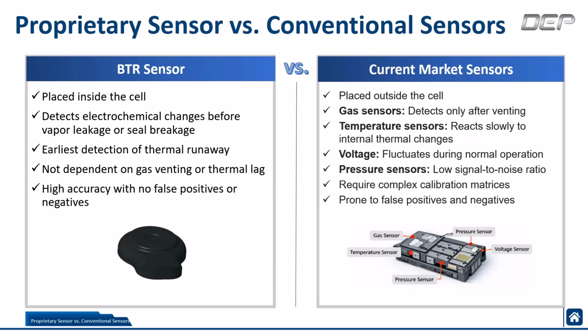To accommodate for the downsides of these sensors, there are combination thermal runaway sensors that are built with some or all of these to reduce their variability. These result in complex calibration matrices across all the detection types and can result in false positives and negatives. Our sensor, on the other hand, is not like these other ones. It's not placed outside the cell, it's placed inside the cell. And it detects the electrochemical changes before any of the vapor leakage or even the relief seal breaking on the prismatic cell. So this gives us the earliest detection of thermal runaway because it's not dependent on any gas venting or any thermal lag. And due to this, it also gives us a high accuracy with no false positives or negatives.